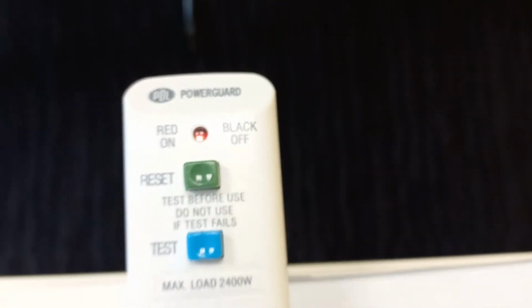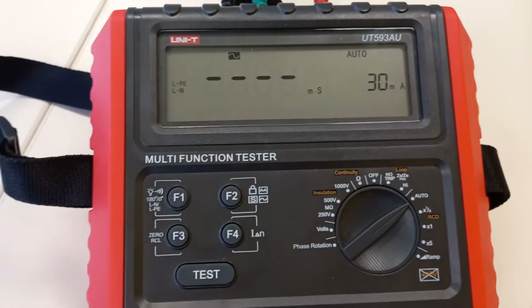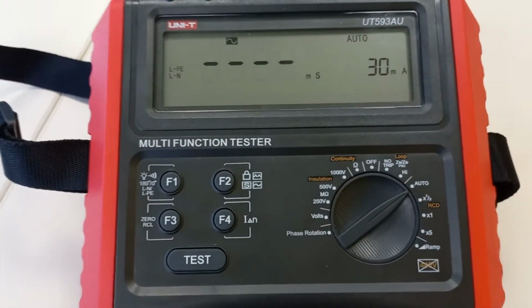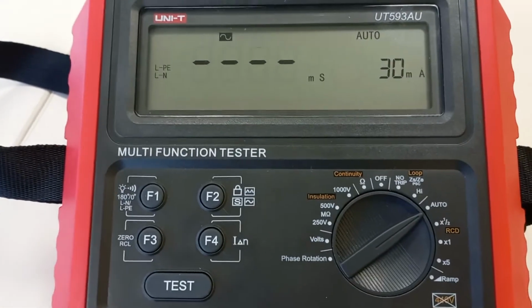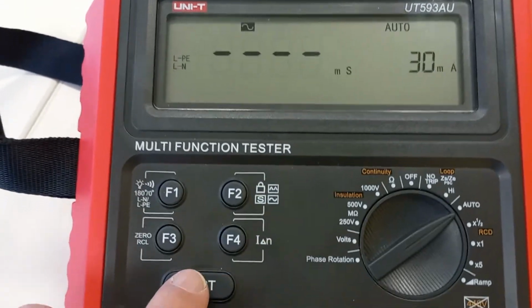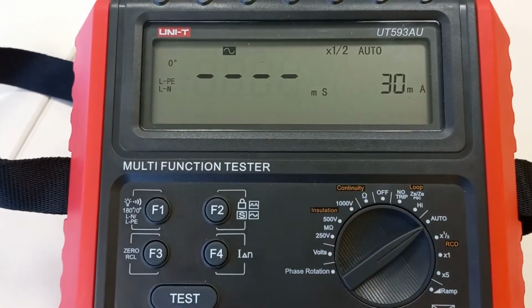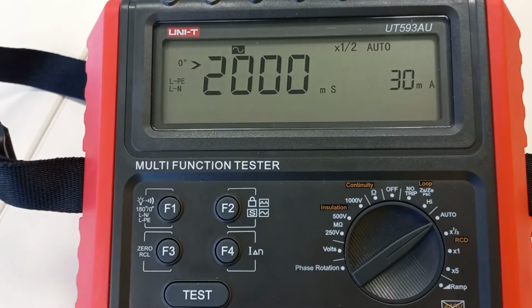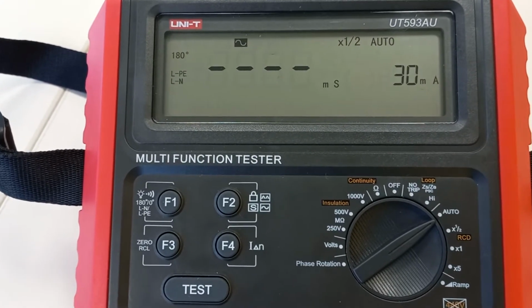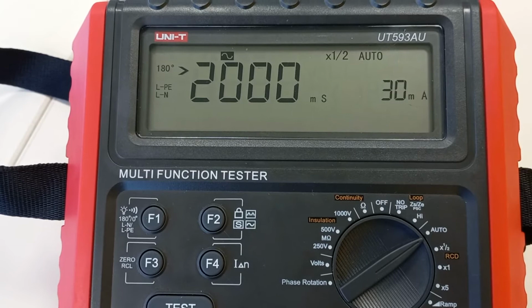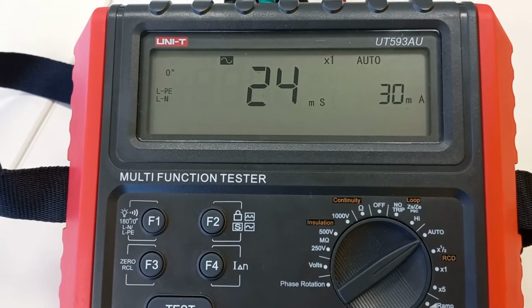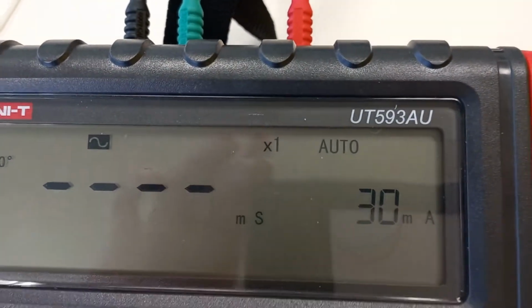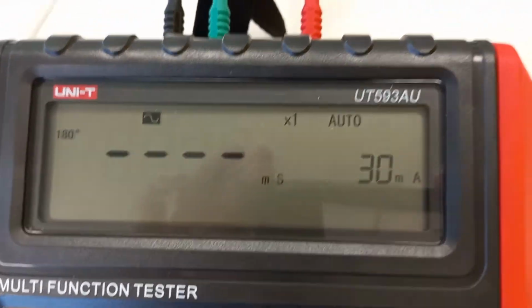Once I reset the RCD, you can see it's reset because we have the orange indicator. That was a little warning to tell me that the RCD was not active. So now when I press my test, it'll carry out the test. The first test is done at half the rated leakage current at 0 degrees, then at 180 degrees. Now it's just gone to the ×1 on 180 degrees, and I'm just going to reset.